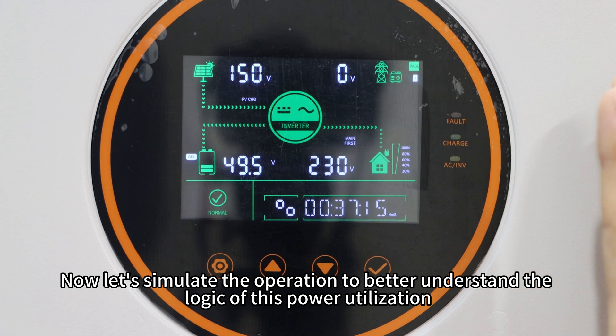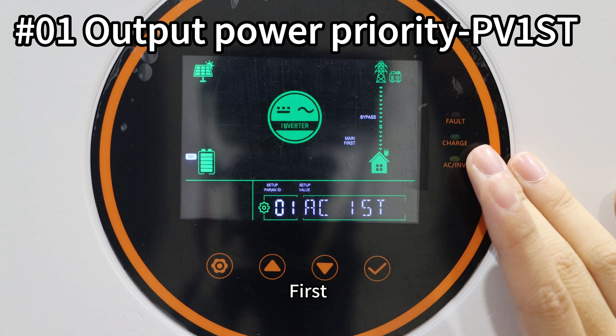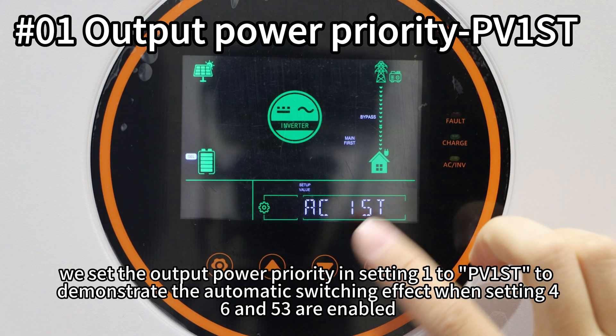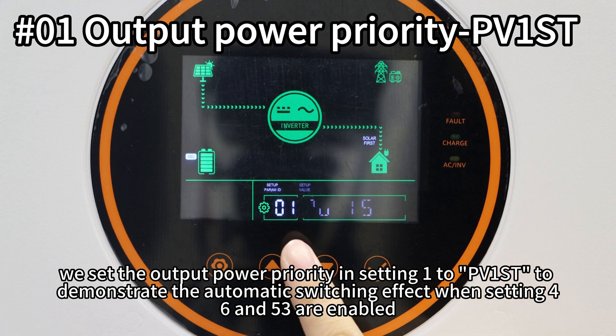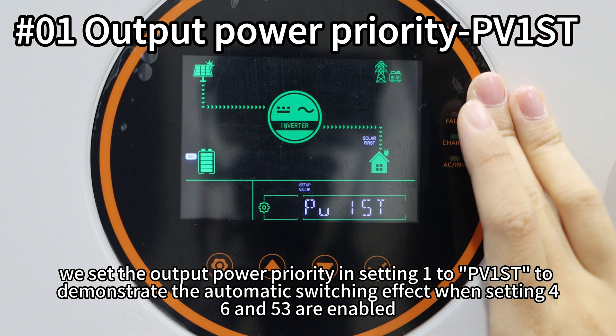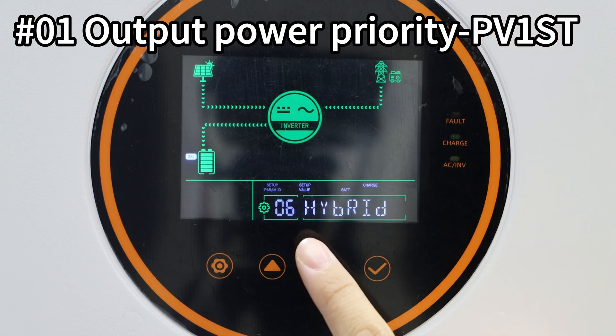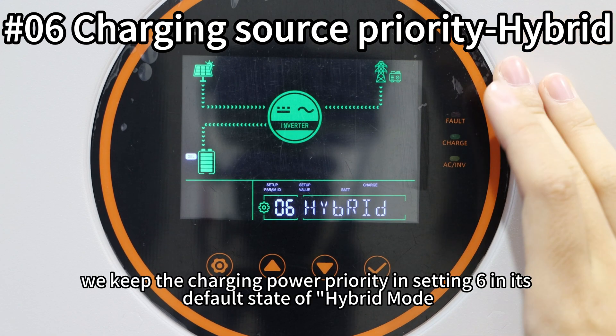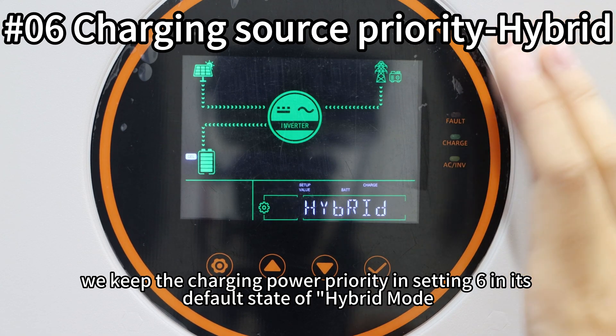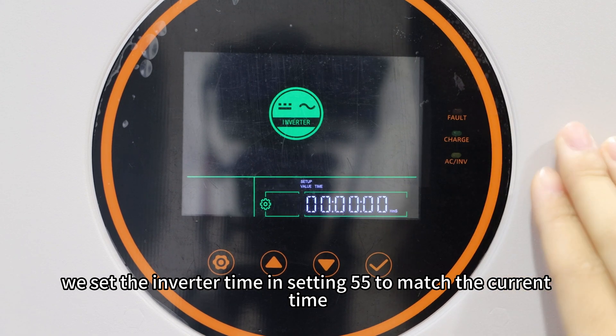Now let's simulate the operation to better understand the logic of this power utilization. First, we set the output power priority in setting 1 to PV1ST, to demonstrate the automatic switching effects when settings 4, 6, and 53 are enabled. Then we keep the charging power priority in setting 6 in its default state of hybrid mode. Next, we set the inverter time in setting 55 to match the current time.